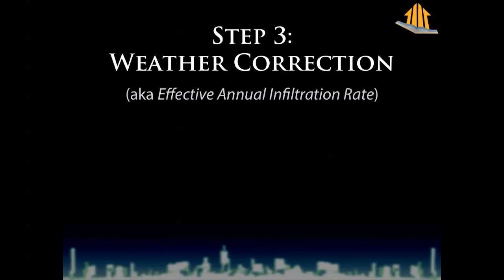So then the next step after we have that normalized leakage for the height correction is we're going to weather correct it for weather and shielding. This is also called the effective annual infiltration rate. So you take your normalized leakage, multiply it by the CFA, the conditioned floor area, and then you multiply that by the weather and shielding factor, which is in orange there. Then you divide that whole thing by 7.3, which is just a static number. It never changes. It's got a bunch of stuff in that number. You don't even want to know what's in there.